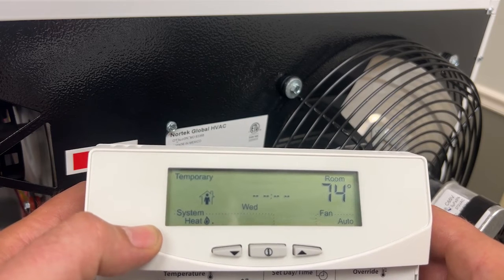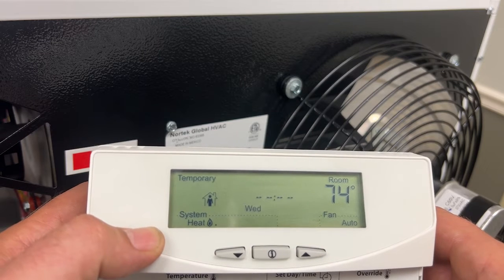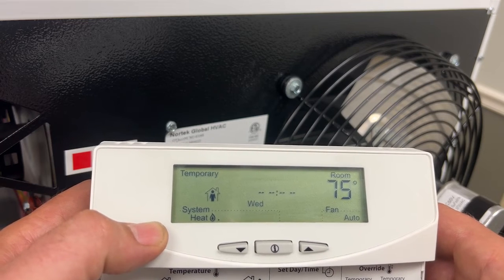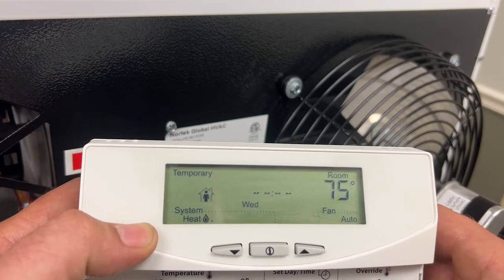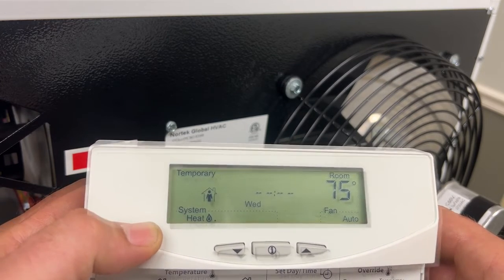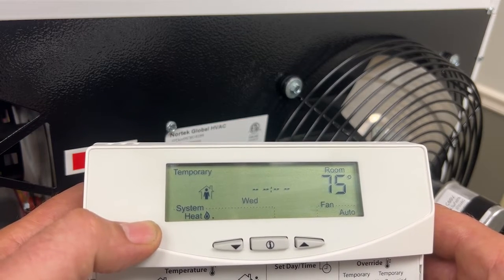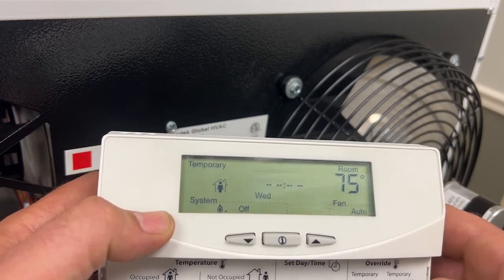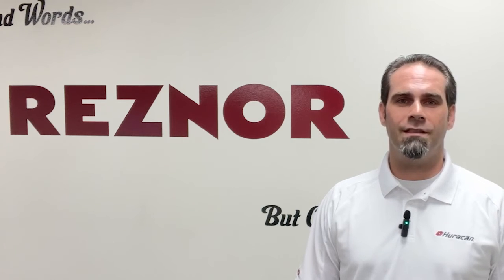Okay let's turn this to heat. Now that we have this turned to heat the venter motor has kicked on and it's going through its pre-purge cycle. I can hear the spark igniter ticking but again I don't have any gas connected to it so it's just going to shut off. Turning it to off — it's going to do a post-purge and the venter motor will shut off. And that's how you connect thermostats to Reznor gas-fired unit heaters. Thanks for watching and we'll see you on the next video.